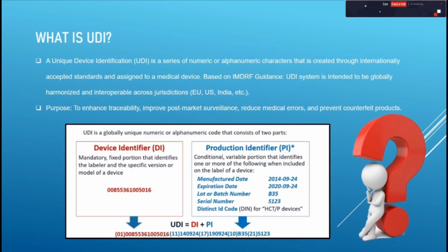Now first comes what is UDI. UDI stands for Unique Device Identification, a globally recognized system for identifying and tracing medical devices. It consists of two parts: a device identifier, DI, which is static and identifies the specific model of the device, and a production identifier or product identifier, PI, which is dynamic and contains production related details like lot number, manufacturing date, and expiry.